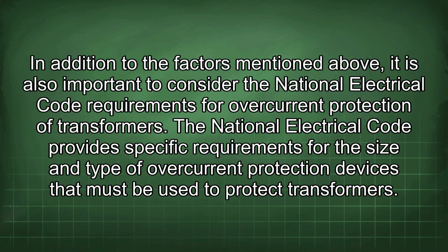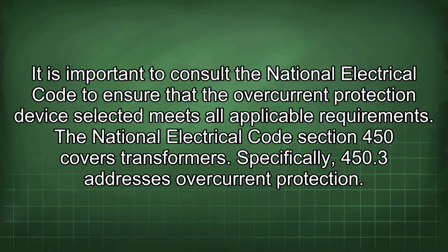In addition to the factors mentioned above, it is also important to consider the National Electrical Code requirements for overcurrent protection of transformers. The National Electrical Code provides specific requirements for the size and type of overcurrent protection devices that must be used to protect transformers. It is important to consult the National Electrical Code to ensure that the overcurrent protection device selected meets all applicable requirements. The National Electrical Code Section 450 covers transformers. Specifically, 450.3 addresses overcurrent protection.